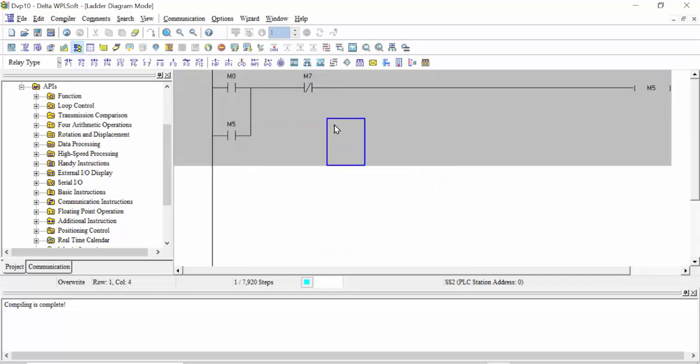Now this bit is changed. Now it's a close contact and this is an open contact. Simply, this is your push button on and this is your push button off, and this is simply M5 you would like to make latch, and this is the open contact of M5. Simply this is your relay look. When you want to make a contactor or relay latch, after that you use the open and close contacts, which are the auxiliary contacts of the contactor.